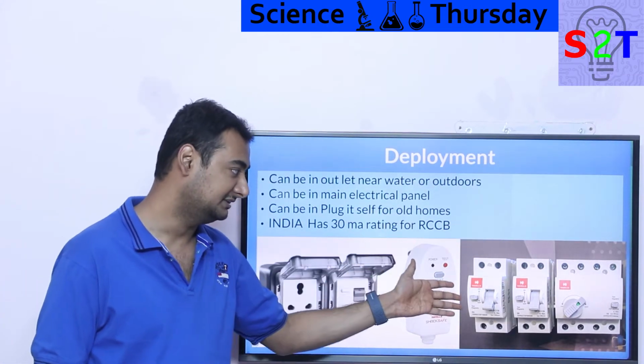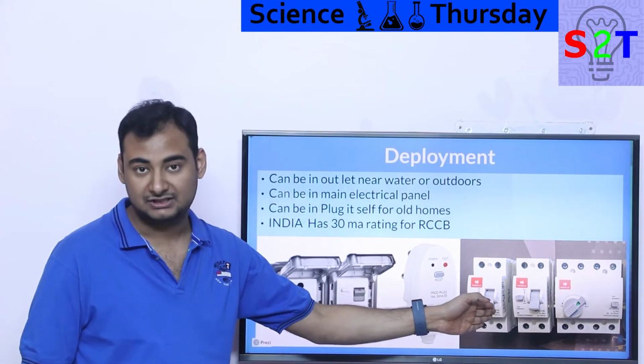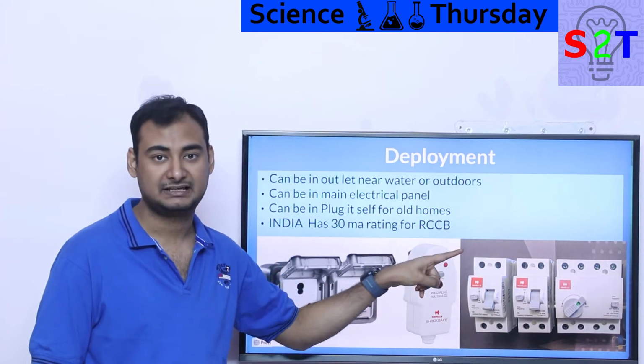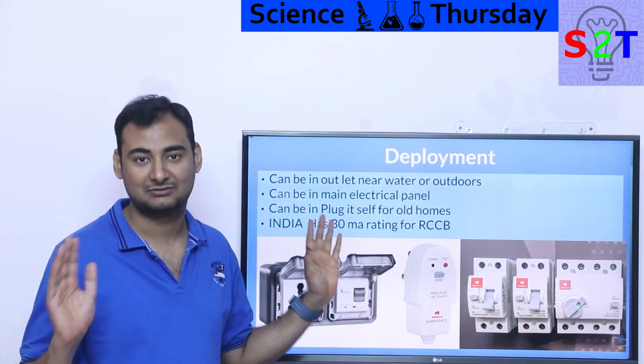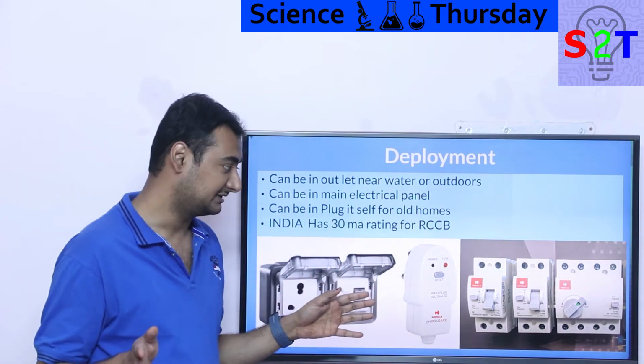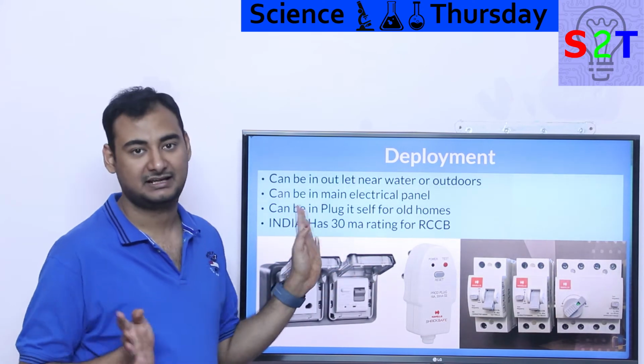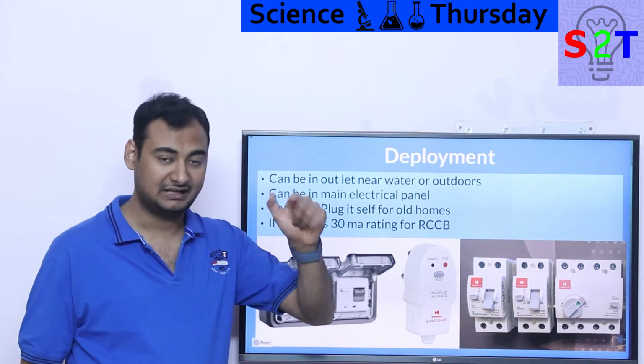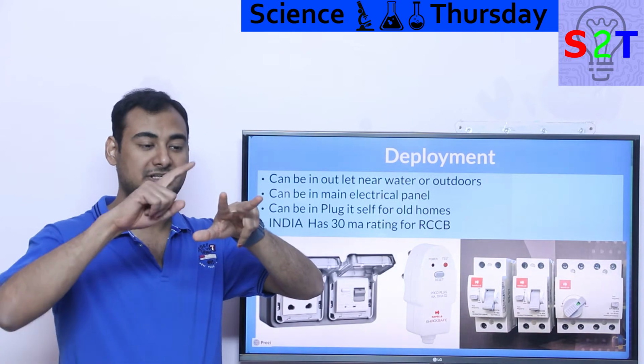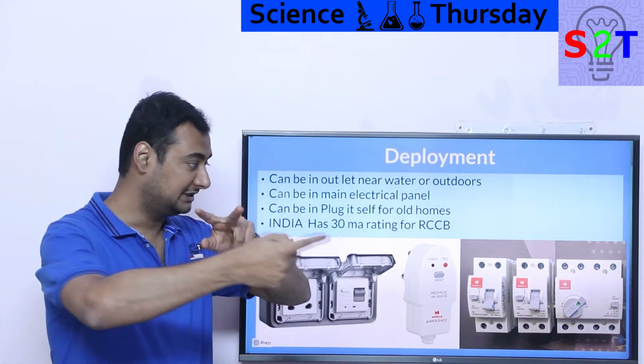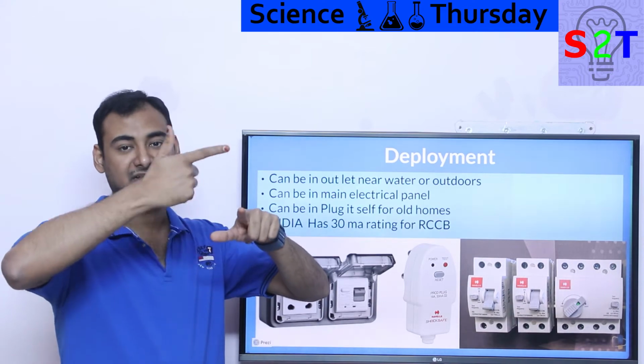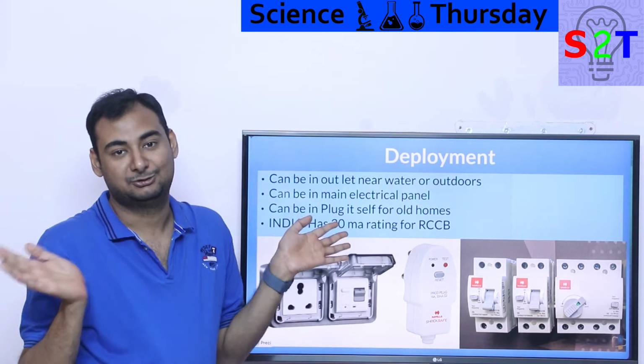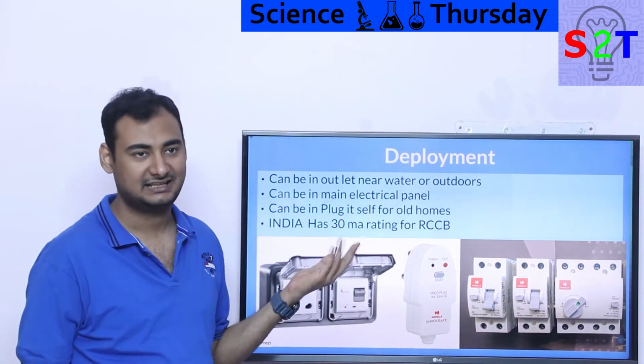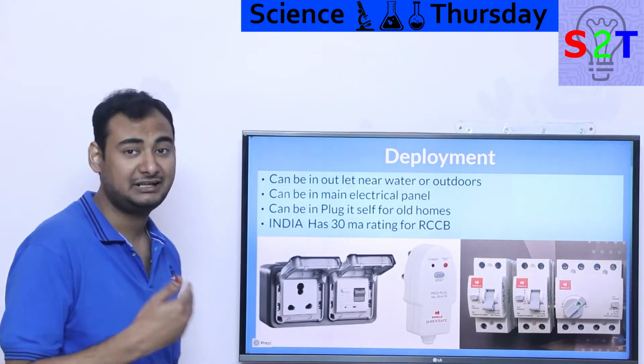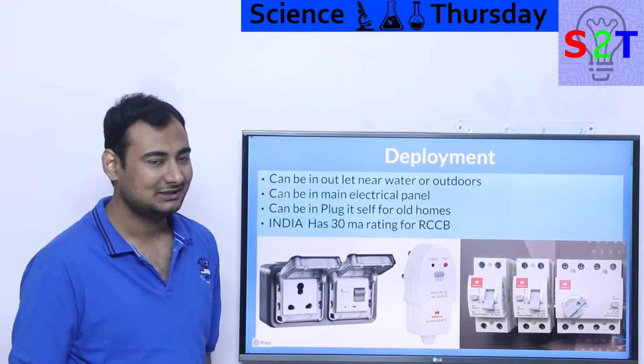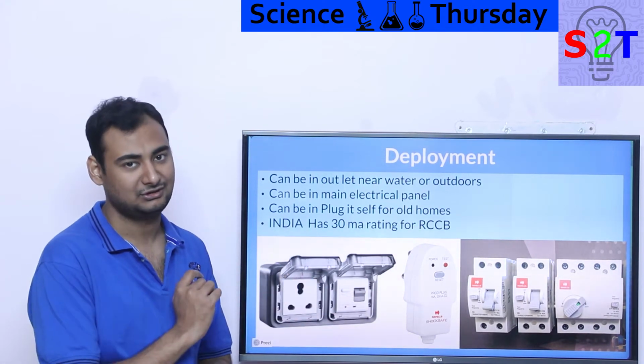You will find devices like this. Now this generally will go next to a MCB. Be mindful, this will not work as a MCB. It does not do anything about overcurrent or short circuit. As long as it's balanced, it's like, I don't care. So you could have a worst case scenario where you have live and neutral, and instead of shorting live to ground, where it will trip, you are shorting between, let's say, live and neutral. This system is like, I don't care. That's one scenario where it doesn't do anything. And even MCBs generally will not trip so early that you would be safe. So that is one fault condition that could happen.